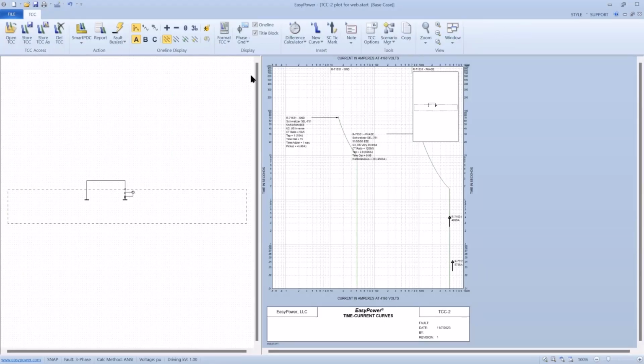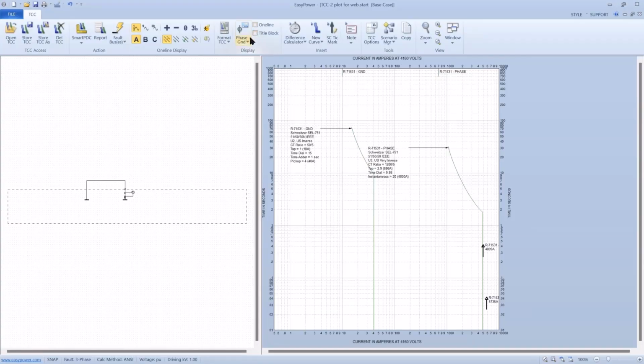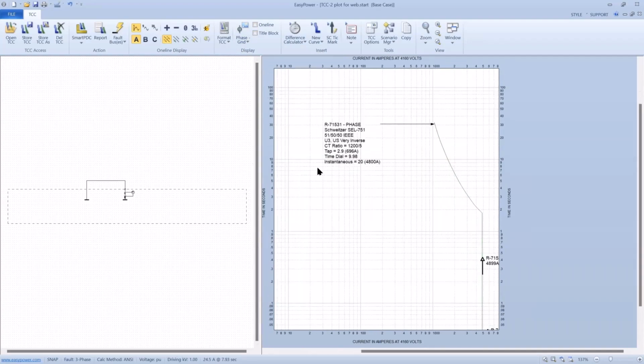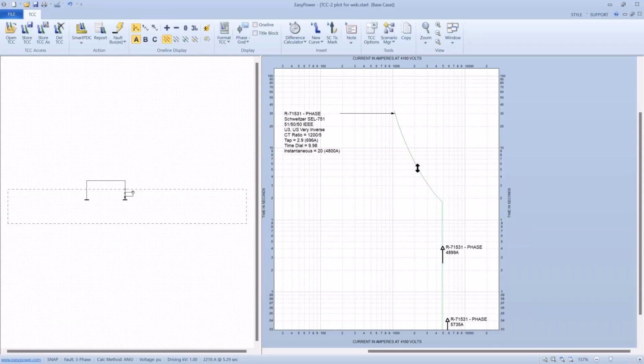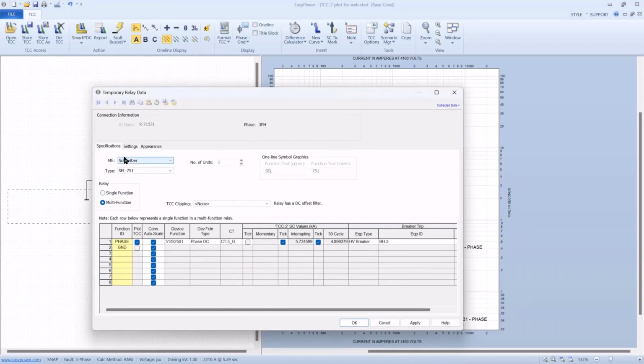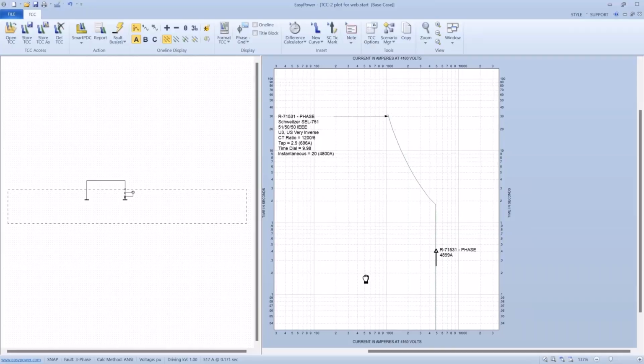Okay, do the same setup. I'm going to ignore ground for right now. Now I've set this relay for a tick mark. I'll open the dialog box. In the settings page, specification page, in the spreadsheet here, there's check boxes that generate the tick mark. So traditionally things are in momentary current, but because I'm doing such a gap in my coordination, I really want to look at 30 cycle.